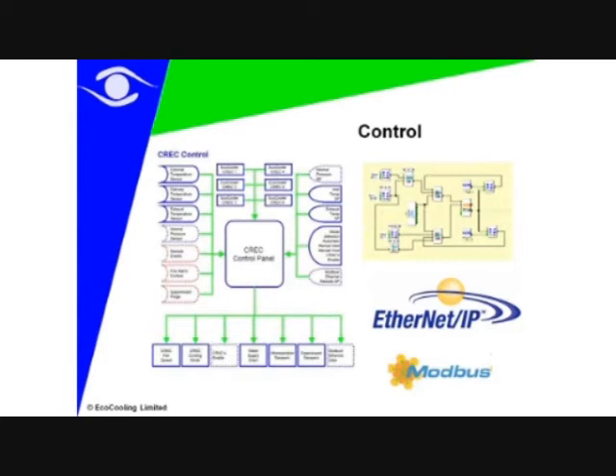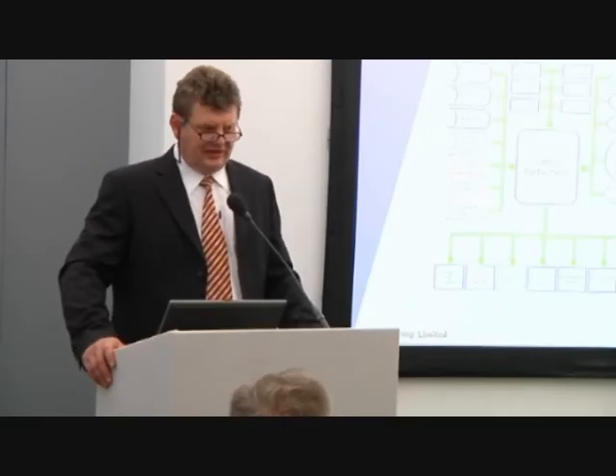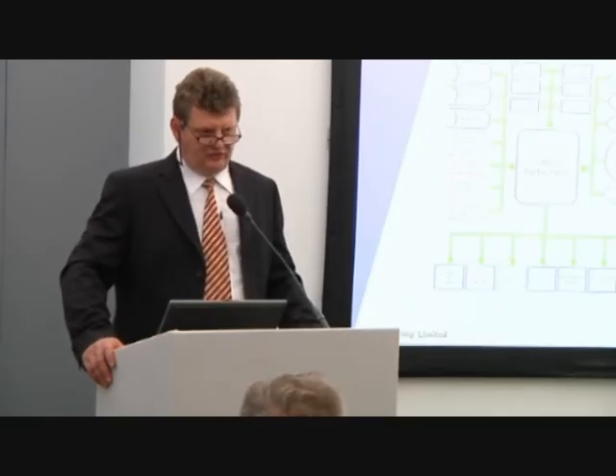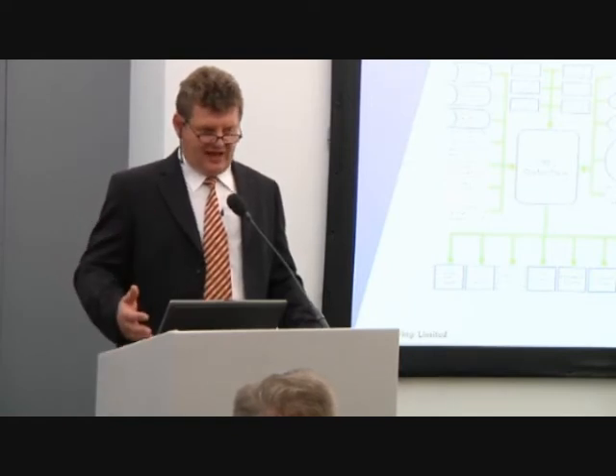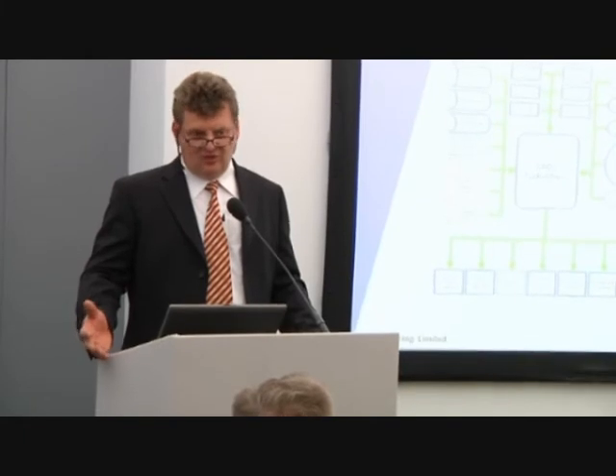Within the CREC control panel, these PLCs use a microprocessor controller operating with Boolean logic — AND, OR, NOT gates. But that gives us full analogue control. We can measure true temperatures, true pressures, and true conditions. And that's all linked together with an Ethernet link into your existing network systems, or using building management systems and Modbus to communicate operating parameters of temperature, pressures, and fault conditions.